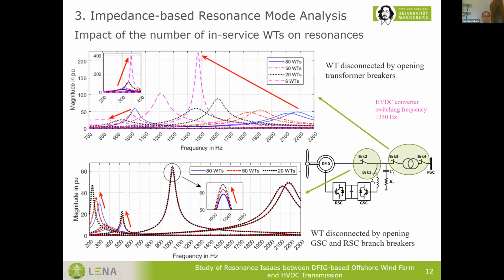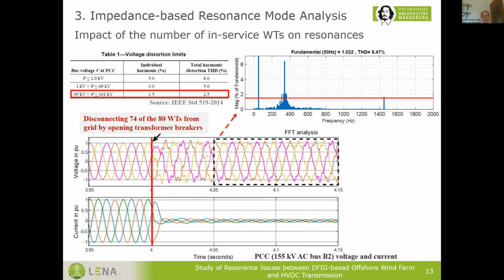Then these two sharp resonance peaks are validated through simulations. As can be seen in this PCC voltage and current waveforms, after disconnecting 74 wind turbines from the grid by opening transformer breakers, large harmonic distortions are observed. The FFT analysis to this time window shows that the 7th and the 29th harmonic component violate the harmonic distortion limits as recommended by this IEEE standard.